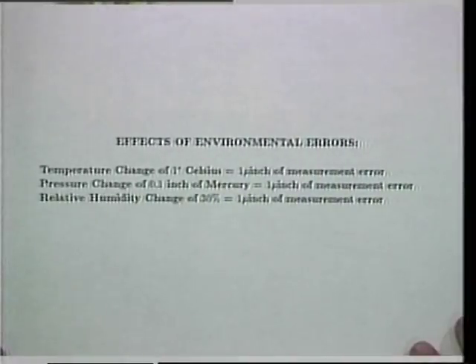Shown here is another way of expressing these effects. For every 1 degree Celsius temperature change, expect 1 microinch of measurement error. For each 0.1 inch of mercury change in the barometric pressure, expect another microinch of measurement error. For every 30% change in humidity, figure on yet another microinch of measurement error. The effects of environmental error can be reduced by manually changing the environmental parameters on the measurement unit or through the use of automatic velocity of light or refractive index compensators.